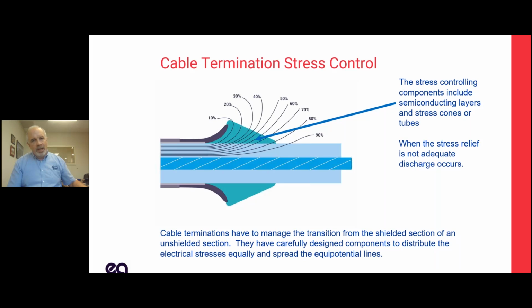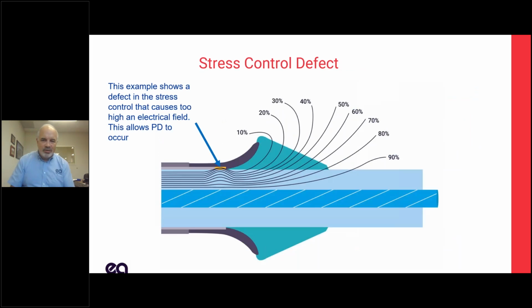Because if we have a defect in the actual termination, let's say, as this picture shows, a gap, an air void in the insulation. They didn't do the termination right. They didn't follow it right. That has a different permittivity, so it allows the concentration of field. Also, air has much lower withstand capability than XLPE, so I've got a bigger electric field and poorer insulation. I'm going to have a flashover.